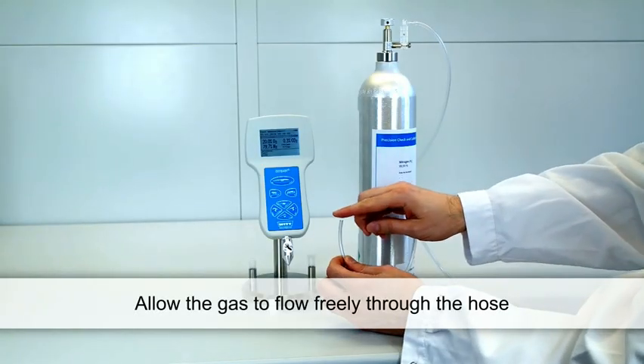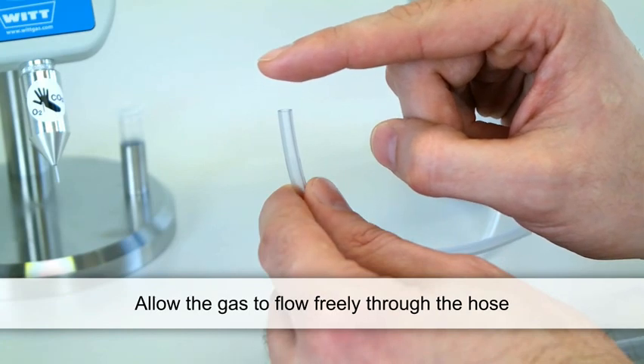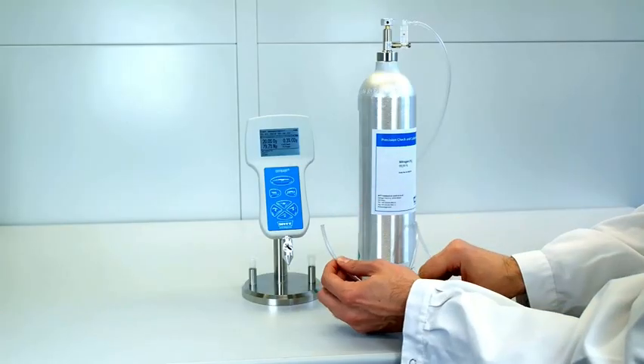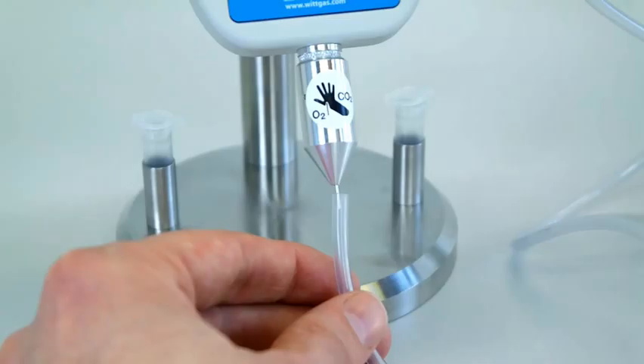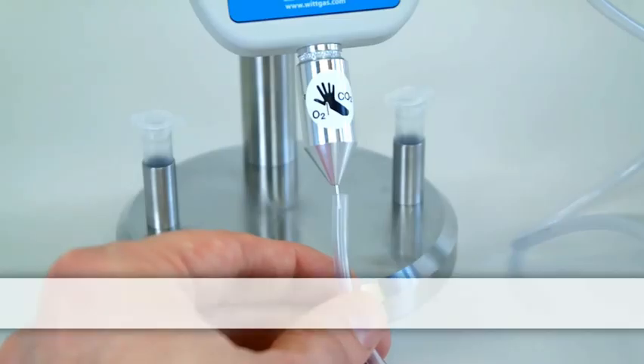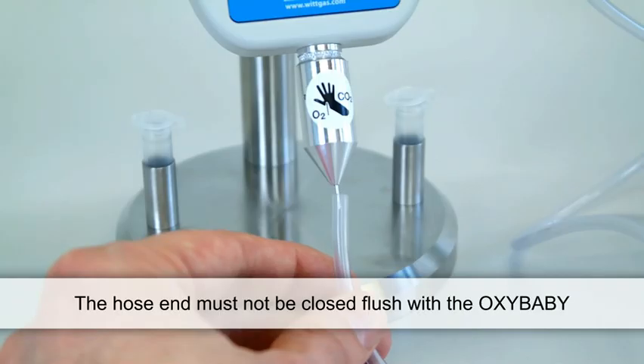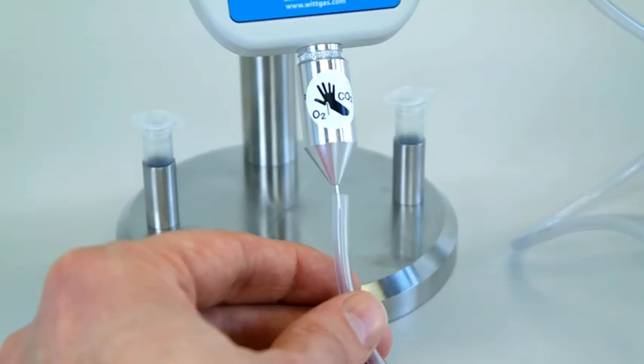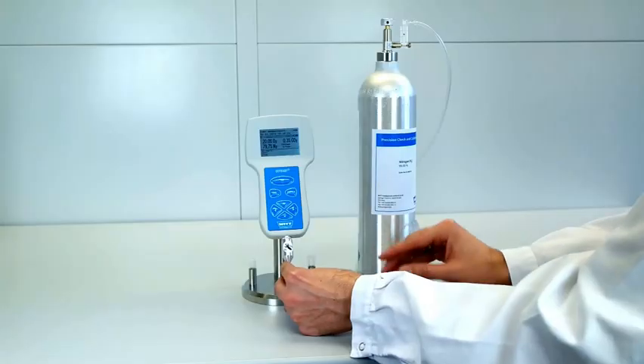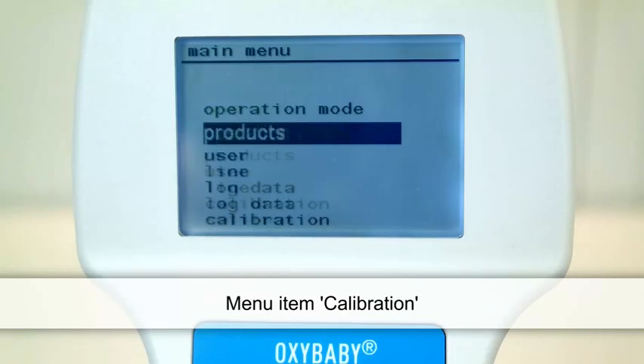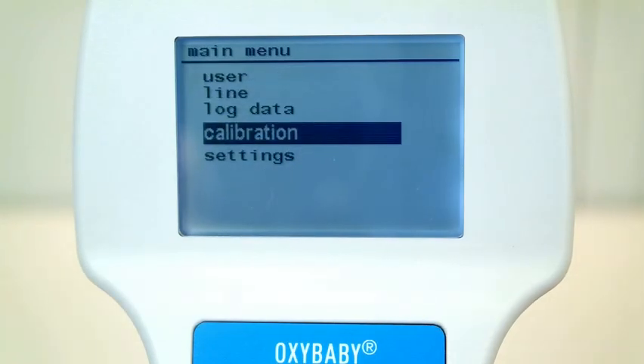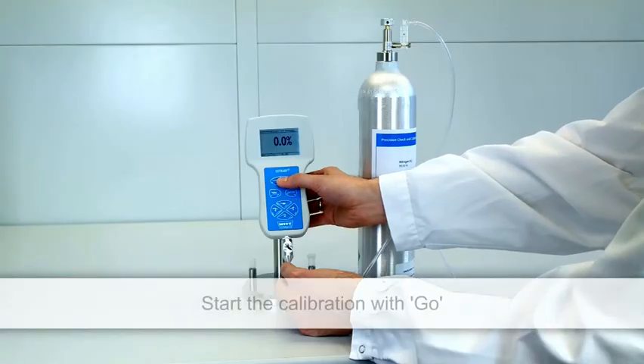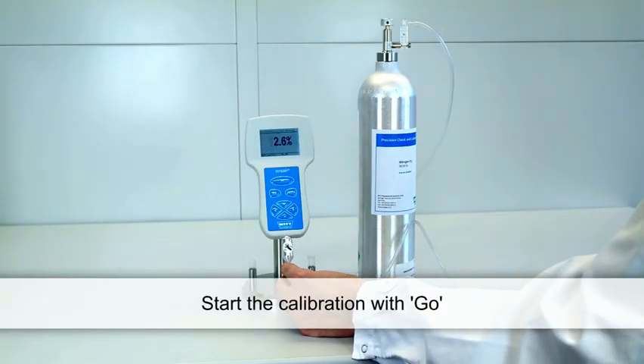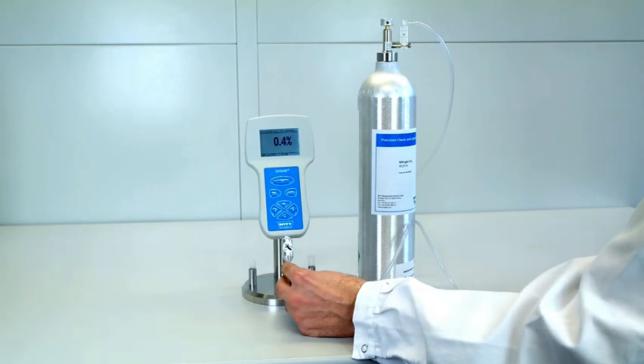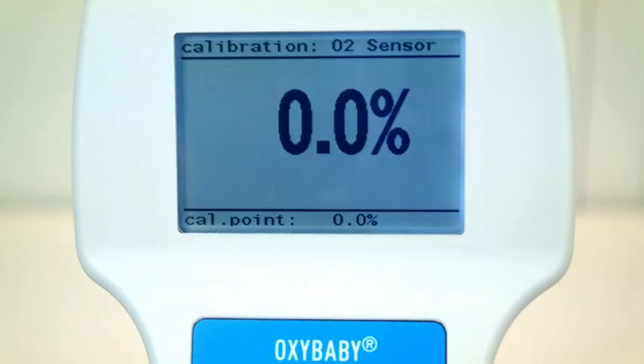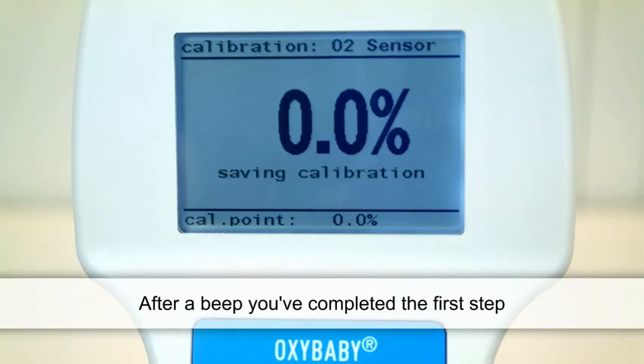Allow the gas to flow freely through the hose. You may test the flowing gas, for instance, with your finger. Insert the Oxybaby needle into the hose so that the Oxybaby can acquire the gas. Make sure that the hose end is not closed flush with the Oxybaby, otherwise pressure could build up and the Oxybaby could be damaged. Use the arrow keys and the Enter key to select the menu item Calibration and then select O2 sensor 0%. Press the Go button to begin the calibration. Once you hear a beep, you've completed the first step.